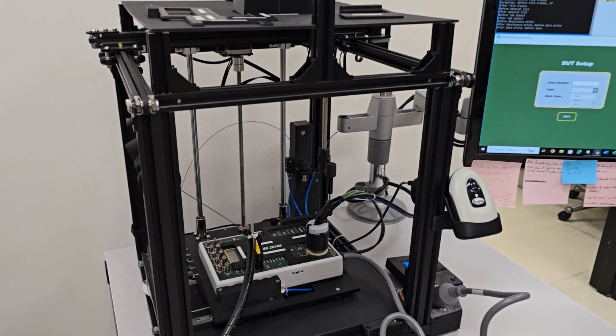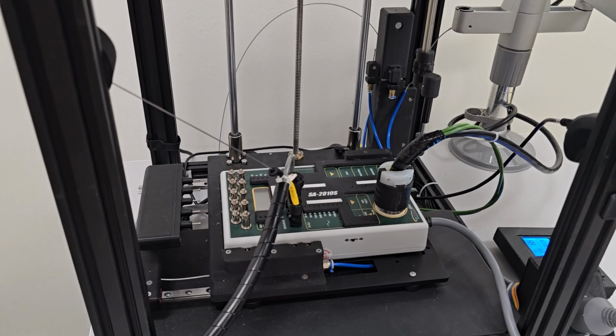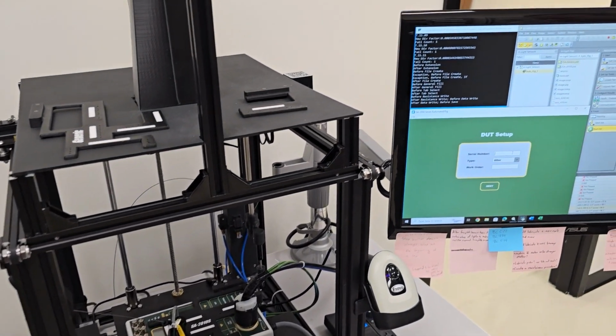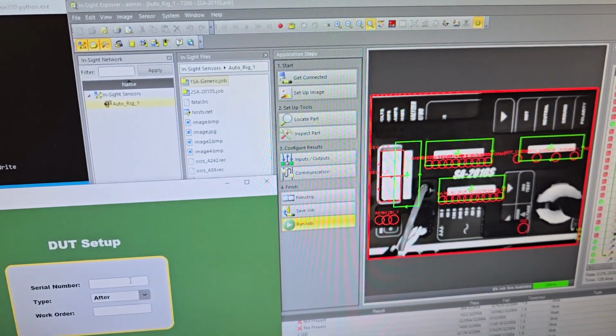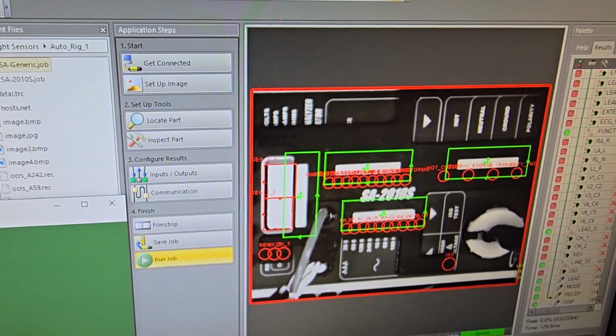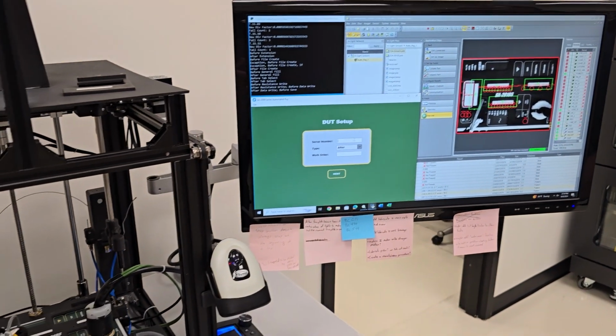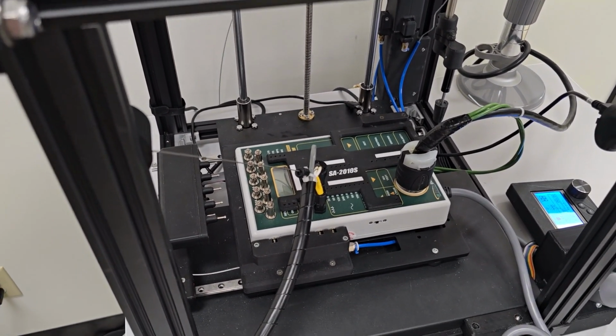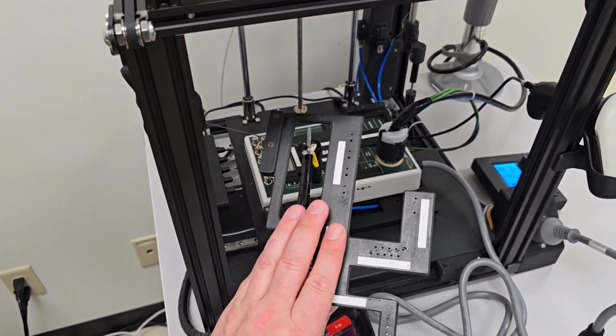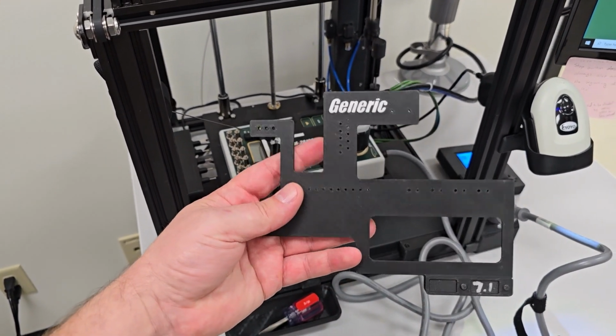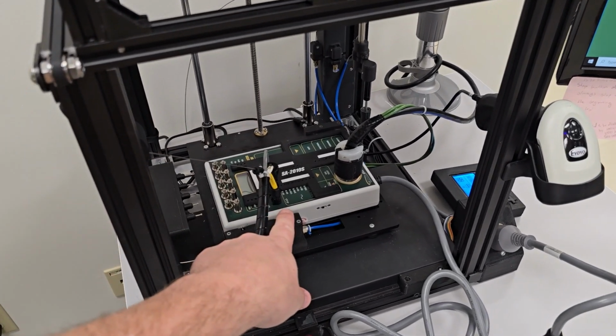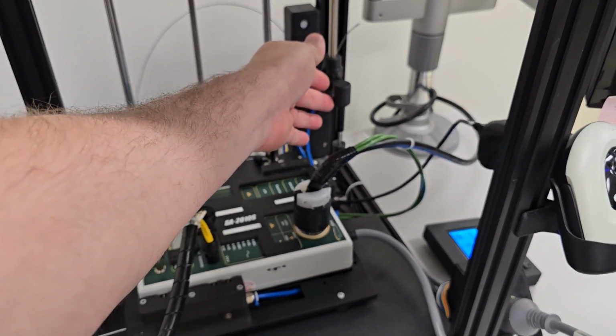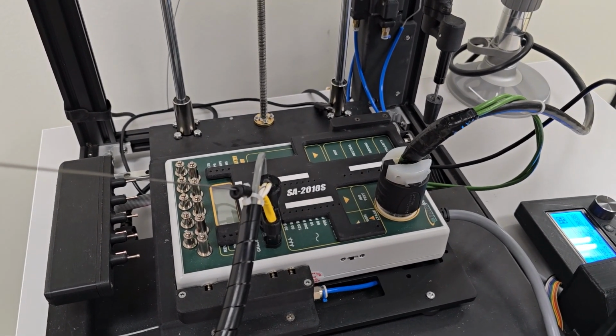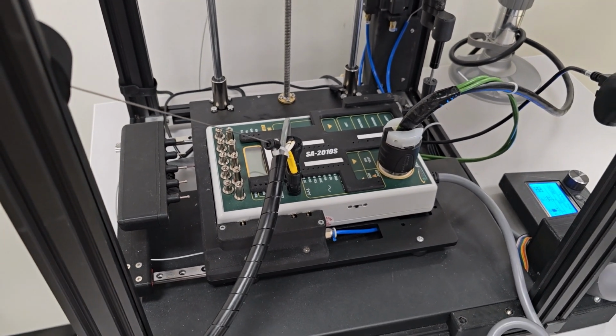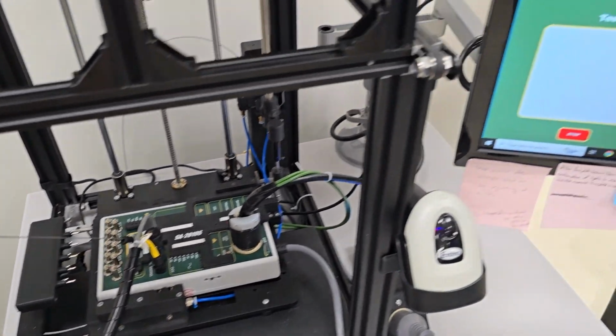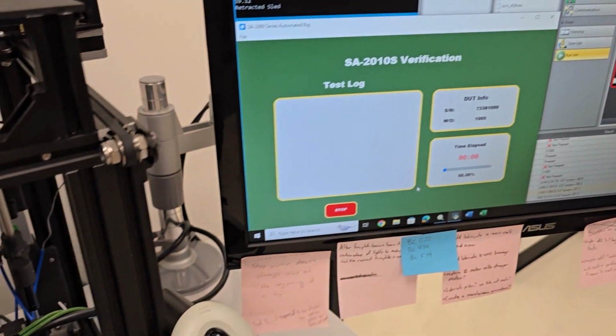Right. Look at this. So we can enter the serial number for our product. Oh, look at that. It shows you a representation of what the camera's seeing. Right. And is it looking for the lights? It's looking for all the lights. It knows whether the polarity is forward or reversed, whether the hot and neutral are on or off. Very cool. Depending on what you're testing, you put a different blank down over the surface, and that makes sure only certain areas have perforations. So when a mode on the electrical safety analyzer is activated, which is this, a finger? That is a finger. So we're going to go ahead and start it off here. The finger is going to enter a mode, and then it's going to test. And the camera is going to look to verify that the mode is activated using software. So now it's connecting the ECG posts. It's going to get to the right mode.